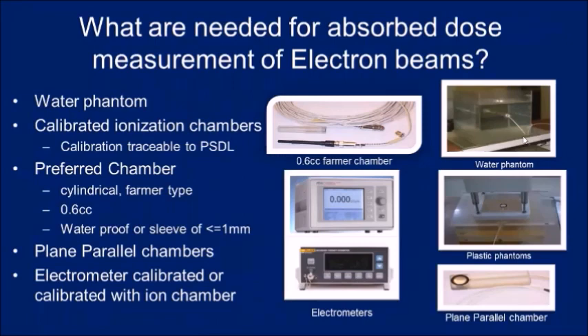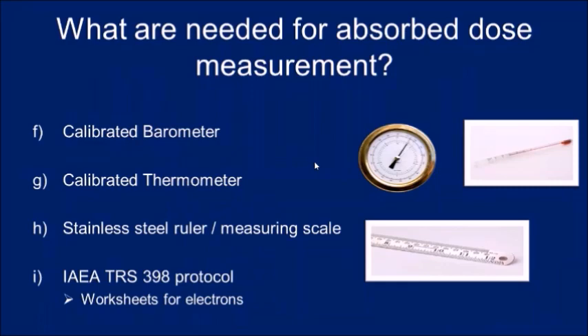So you should have a plastic phantom, water phantom, plane parallel chamber, cylindrical chamber, and electrometers. In addition you need a barometer and thermometer — both should be calibrated to measure pressure and temperature — and a ruler to measure depth, preferably a stainless steel ruler, along with the IAEA TRS-398 protocol and its worksheets.